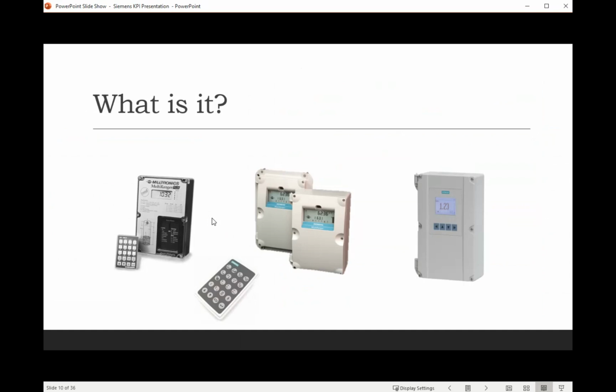Most of what you see today is the Hydroranger in the middle. There's still a couple of the Hydroranger Plus, Multi-Ranger Plus out there, but the one in the middle is what we see most often out there. It's programmed with a handheld remote, and then recently, within let's say the last 5 years, the HMI version, which is the Hydroranger on the right, with the 4 push buttons, has been introduced, and it's made it a little bit easier for us. So when it comes to the Hydroranger, it comes in a 1, 3, or 6 relay model. It has the ability to take in 1 or 2 transducers, and it all depends on the model.